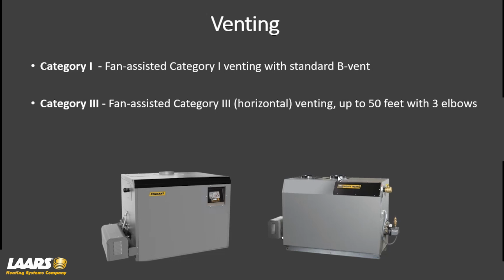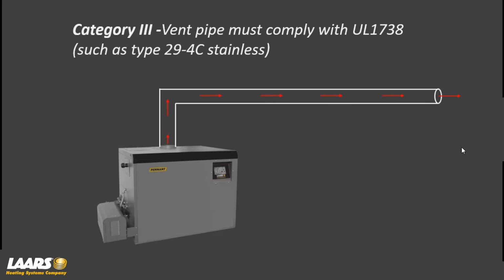Category 3, we can go up to 50 feet with 3 elbows horizontal venting. Now, that vent for category 3 must comply with UL 1738, stainless steel gas tight, such as 29-4C. Why? Because that is under positive pressure. And if you had seams that leaked like a B vent, you could blow flue gases right back into the space. So read the manual on this. Again, up to 50 feet with 3 elbows is allowed.